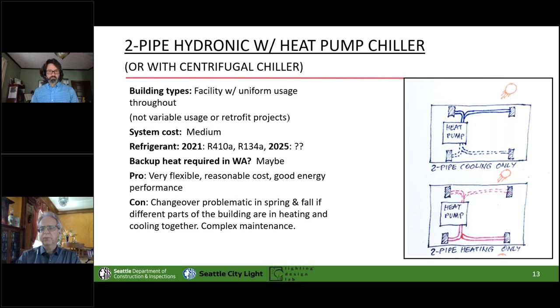But here we got a two-pipe chiller, and I was trying to come up with a diagram. You could kind of see this looking from the top of a building with the heat pump. If you're going to do a two-pipe system, it saves you a lot of money over four-pipe, but you've got your choice: everything is in cooling or everything is in heating, right? Right. And so if it's once again the October morning and the east side is cooking and the west side is still kind of frosty, you could have unhappy people in your building.